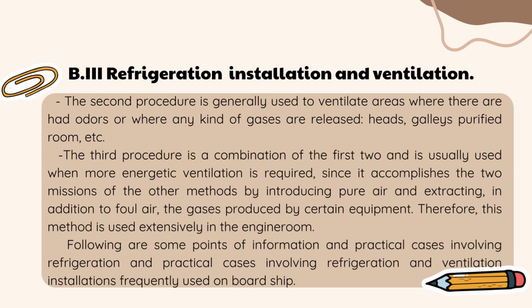The third procedure is a combination of the first two and is usually used when more energetic ventilation is required, since it accomplishes the two missions of the other methods by introducing pure air and extracting, in addition to foul air, the gases produced by certain equipment. Therefore, this method is used extensively in the engine room.